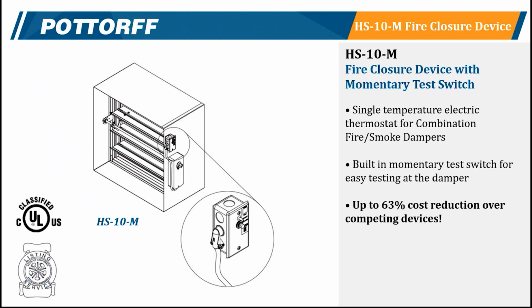Because there's no required position indication, and because we're using a single junction box to house everything, it's really tough for us to put the lights in there. To have the thermostat and the lights and everything in the same box is just too cluttered. So we still want you to go back and use the RCP1 or the RLPs if you need lights, or the RCP1M if you just need a momentary switch. Because it's a momentary switch, we expect you to have access to the damper to push that button, hold it down, have the damper cycle, get through your NFPA 80 and 105 cycle testing, then release it and have the damper work as designed, normally open and fail closed.